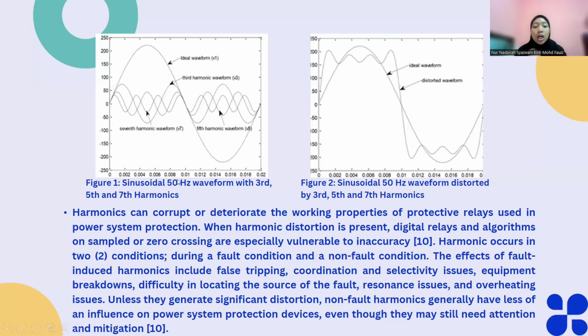As we can see here, figure 1 shows the sinusoidal waveform for 50 Hz with third, fifth, and seventh harmonics. This is the ideal waveform, which is the original waveform, and the third, fifth, and seventh harmonic waveforms show differences in the amplitude and the period each cycle takes to complete. Figure 2 shows the sinusoidal waveform for 50 Hz distorted by the third, fifth, and seventh harmonics. As you can see, there are differences between the ideal waveform and the distorted waveform, including in the amplitude of the waveform itself.